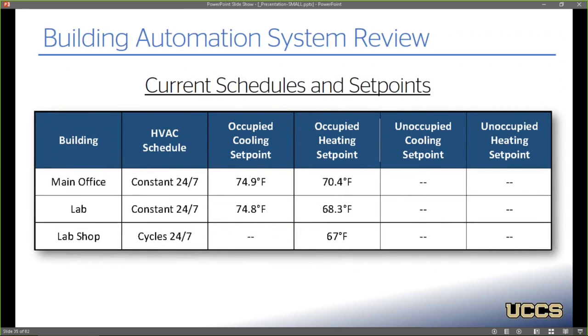This is a summary of their current schedules and set points. Everything's operating 24/7. The lab shop cycles 24/7. The set points are weighted averages based on peak cooling airflow provided to each space, and they're largely appropriate. Around 70 in heating, around 75 in cooling.